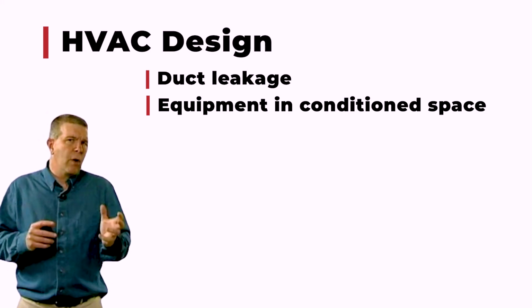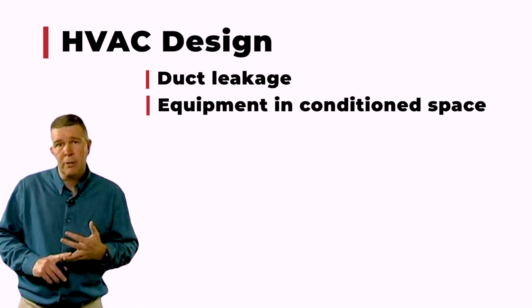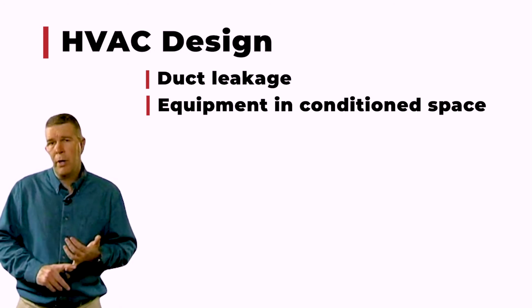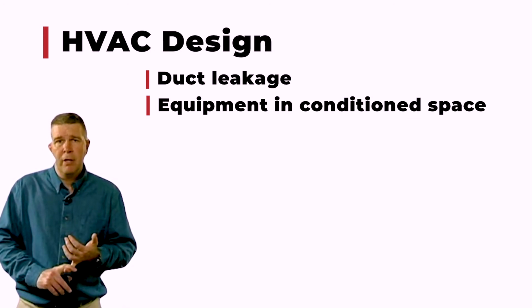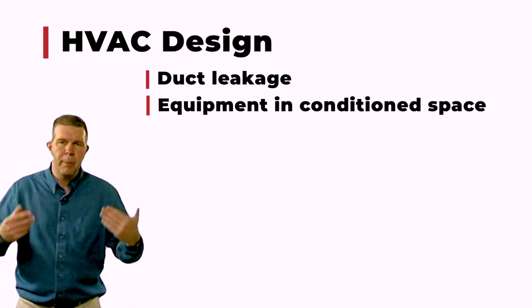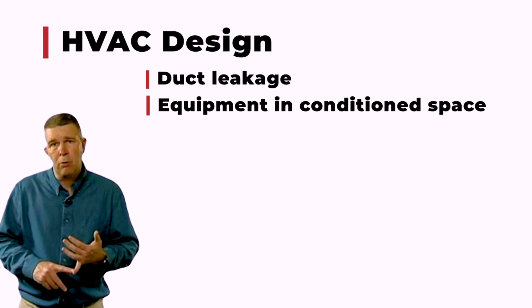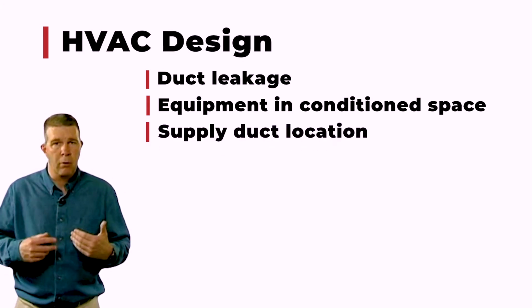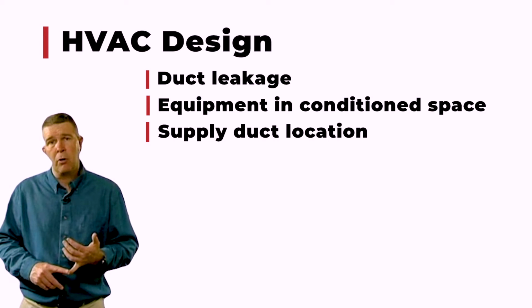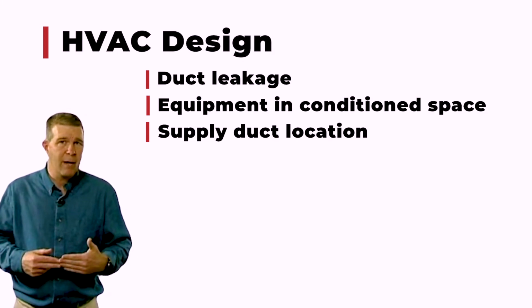So you have to understand where this equipment gets located, what the duct size is, how much air is flowing through it, where the registers and the supply ducts are, where everything is located so we get proper air movement. We also don't want to use that old traditional method of putting all of our registers or our ductwork out to the exterior envelope above windows and doors. It put in that curtain of comfort. They wanted to put that warm or cool air in front of the old leaky windows and doors. Well, the windows and doors that we use in today's house aren't old, they're not leaky, they're high-tech. They use high-tech materials. They're well sealed when they're properly installed. You don't have that cold area when standing in front of a window or a door. So we don't necessarily need that register right above it.